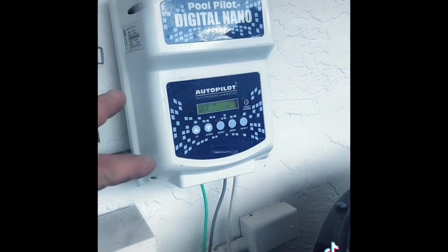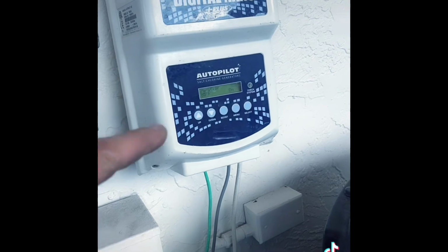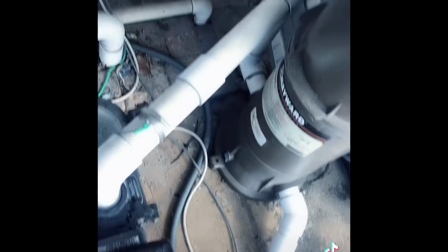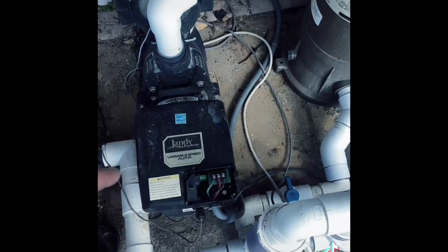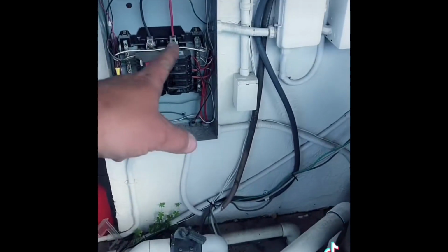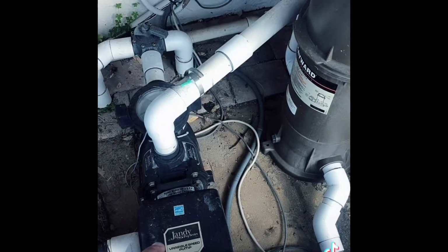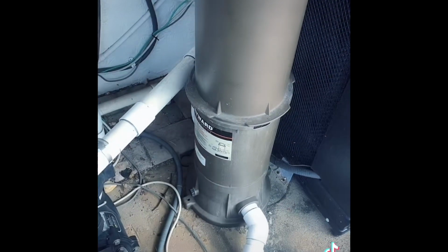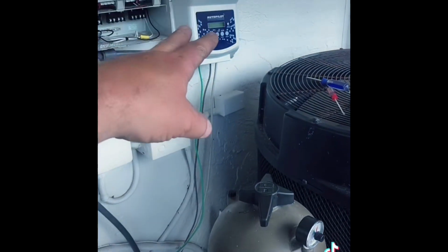And again, the reason why we did this change was because the salt system was wired up to the line side of the pool pump. Originally, the circuit breaker was coming in, feeding the pool pump, and then they teed off of that and went up into the salt system.